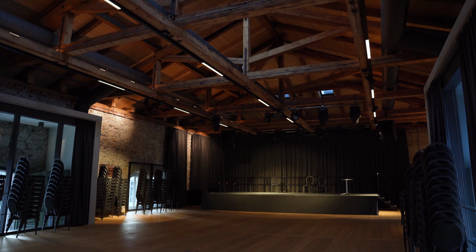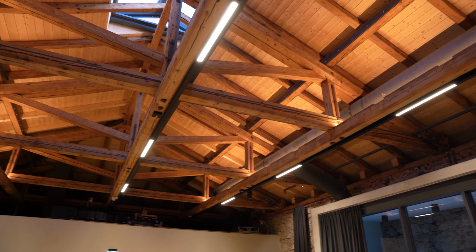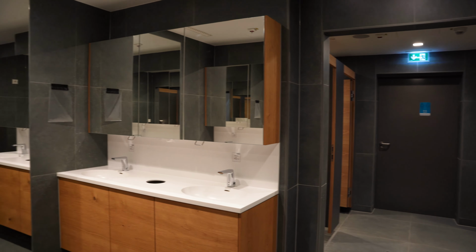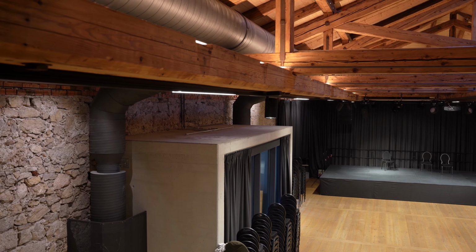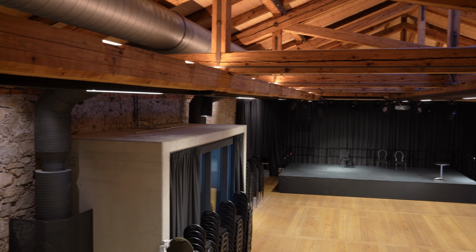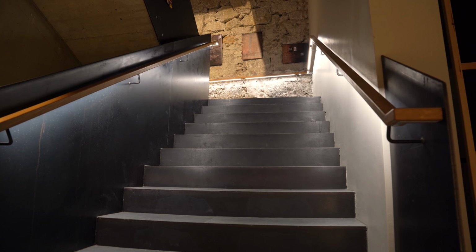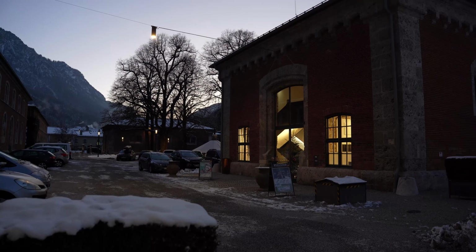Perfect, and aside from the energy challenge, I also see up here a great job with lighting. Exactly, so most of the lighting technology here is through DALI, which is super to integrate into the Loxone system, as Loxone offers the DALI extension. Lighting is now 80% of the time using DALI, but for the rest we used part of a relay extension. The outdoor lighting is also being completely controlled via the Loxone system, including time control, so that in the evening atmospheric lighting turns on.